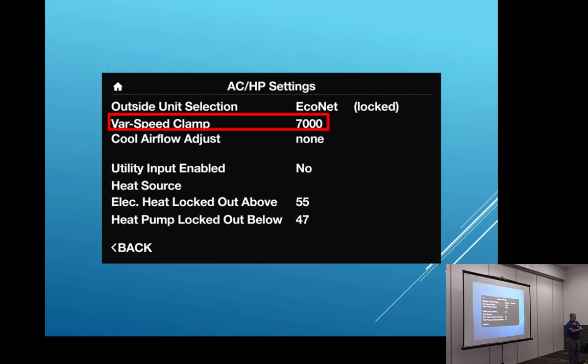AC and the outdoor unit heat pumps. So on the 18 SEER, that 18 SEER compressor is a fully variable speed compressor. And it'll run from 15% up to 120% capacity. Okay? A normal compressor runs at about 3,600 RPM. That 18 SEER will run up to 7,000 RPM. So it just takes a little bit of education with the homeowner and make them aware that it is capable of producing up to 120% capacity if it needs it, if they demand it.